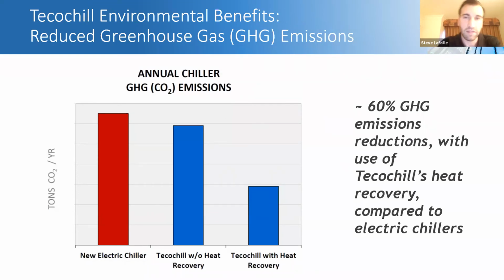When it comes to GHG emissions, you're going to get a minor bump if you don't use heat recovery. That's because the grid is about 35% efficient generation of power at the central plant, with 5% T&D losses, so we're almost neck and neck with the grid if we don't recover the heat. But the moment we recover the heat, we're taking our process efficiency from 30%, which is the engine's efficiency, and raising that up to 80%, because we've recovered all that waste heat from the engine—something the power plant cannot do feasibly, since it's rejecting all its waste heat with no way to use it. So that difference between 80% efficiency of our CHP system and 30% of the electric chiller from the power plant is where you get that huge reduction in GHG emissions.